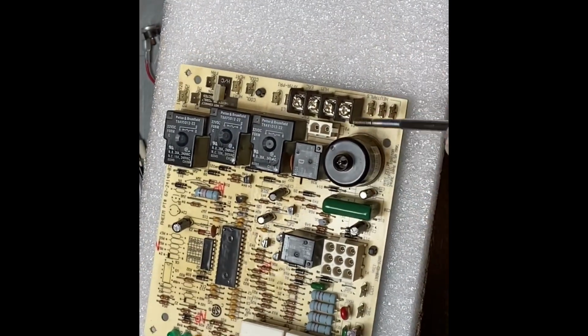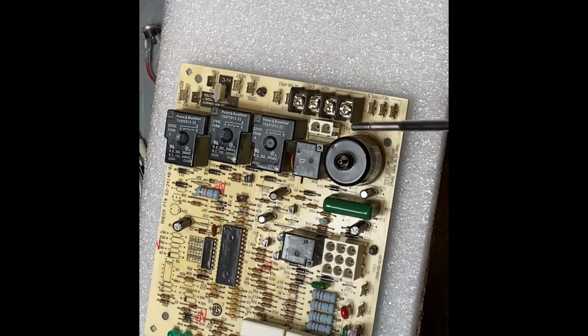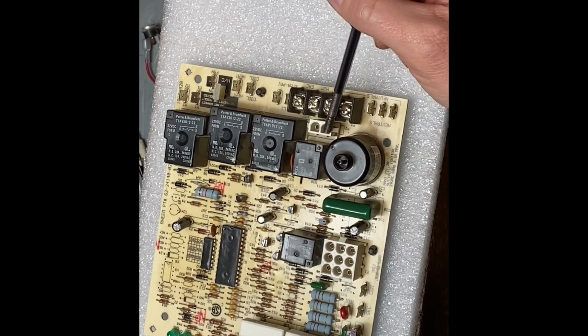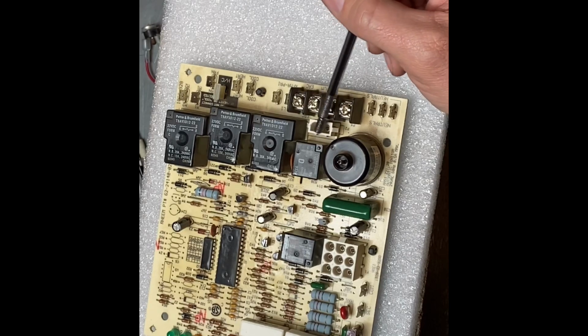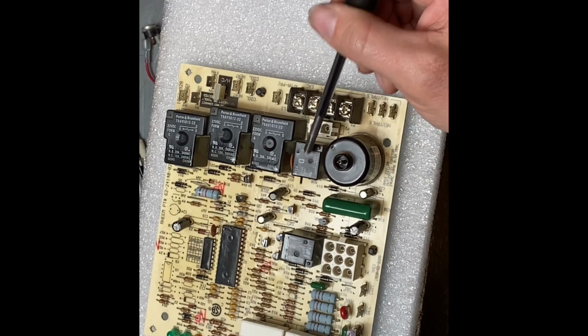Here what we have is our spark igniter. This is a step up transformer. It's very little amperage, but it sets it up to high voltage so that you can actually spark and ignite the flames. These 2 terminals right here are going to go for the inducer fan motor or forced draft motor. And here's the relay controlling this.